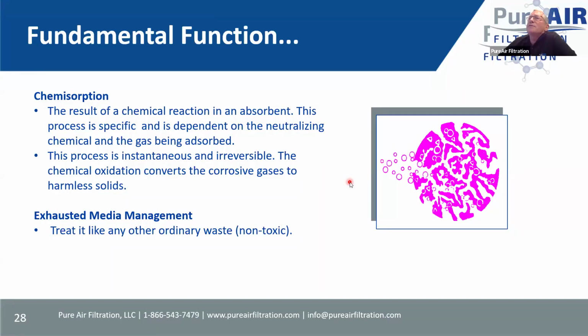The way our media works is basically chemisorption. It is basically a result of a chemical reaction in an absorbent. And this is a sphere of aluminum oxide that is impregnated with a chemical. As the gas passes through the media, there's a chemical reaction that oxidizes and converts the corrosive gases to a harmless solid. In the case of chlorine, we turn it into a harmless salt compound, resulting in something that is treated, as far as landfill and that type of thing, just like any ordinary waste. It's non-toxic and landfillable.